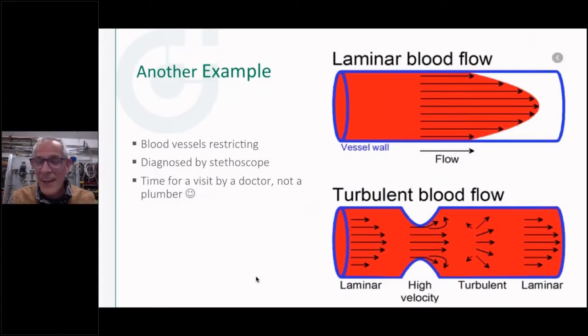And by the way, it's happening as we speak in our bodies. As I was searching for Reynolds numbers and turbulent flow, this came up. Who knew? I didn't know. But the same thing would happen in our body. We want this type of flow condition. And if your veins or your vessels start to plaque up, or you start to get a little bit of scale buildup inside your veins, this is what happens. You get that little choke-down section, just like when we have a balancing valve where we choke the flow down. And now we're going to have a little turbulent condition on the other side of that. You'd probably want to go to the doctor if they think that's happening. They'll put a stethoscope on and go around, and they can detect that just by hearing the condition you get with turbulent flow, when you restrict water, or blood in this case, through a restriction like that. You can see how the flow changes from laminar to turbulent conditions because of that restriction and that downstream turbulent condition.